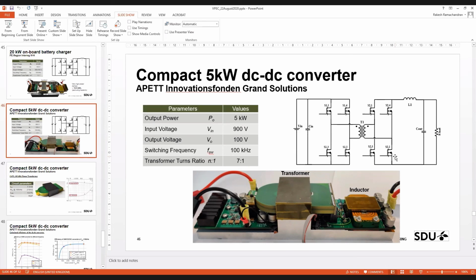You need a snubber. Yeah, you need a snubber on the secondary side, the rectifier side, because the small leakage inductance rings with this capacitance at this point. So definitely you need it, even in phase shift you also need this snubber.